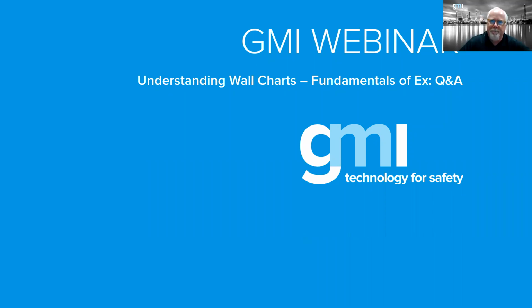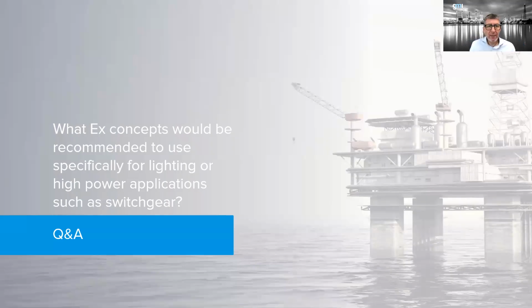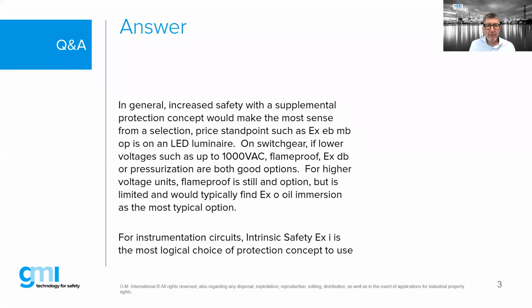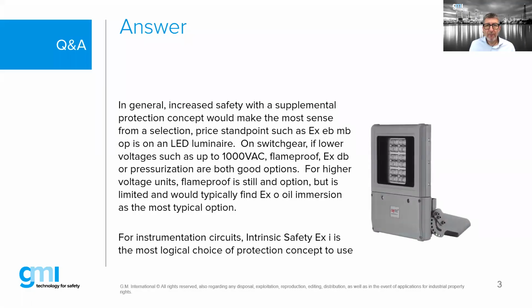First question: what EX concept would be recommended specifically for lighting or high power applications, such as switchgear? Bob, you have prepared this answer. Yeah. Increased safety with supplemental protection would make the most sense, for example, for lighting. A lot of traditional lighting for zone 1 applications was basically flame proof.